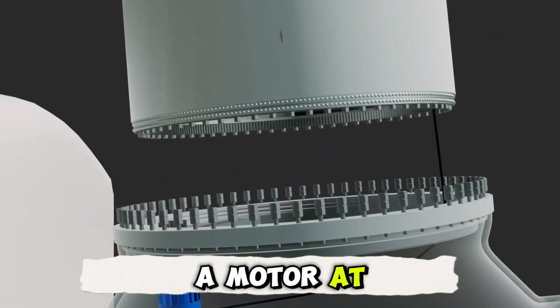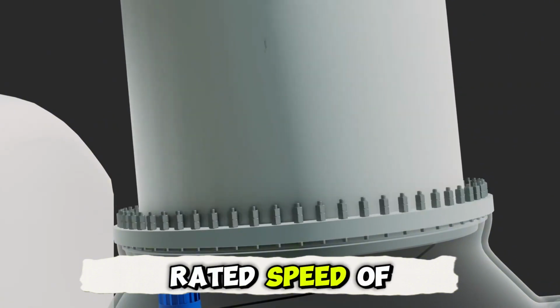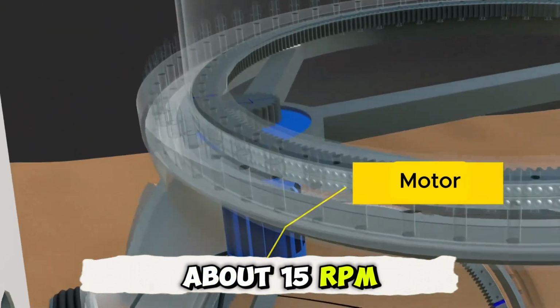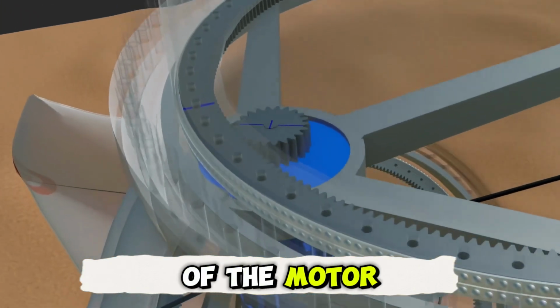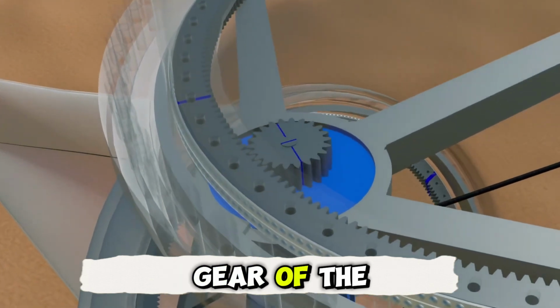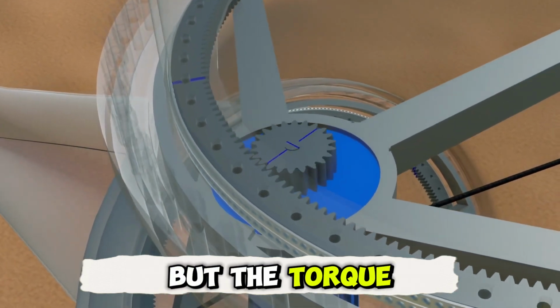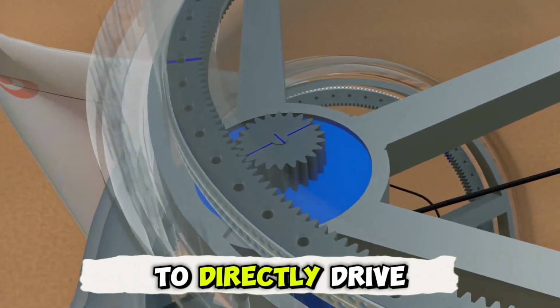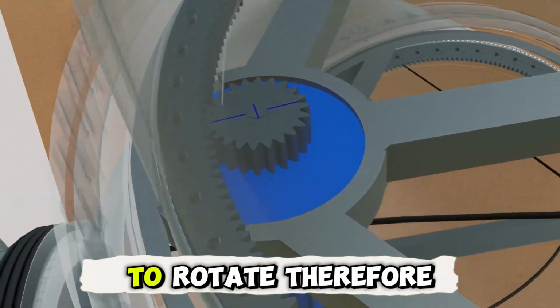There is a motor at this position below, with a rated speed of about 1500 RPM. There is a gear on top of the motor. The gear meshes with the gear of the bearing's inner ring, but the torque generated by the motor is not enough to directly drive the massive blades to rotate.